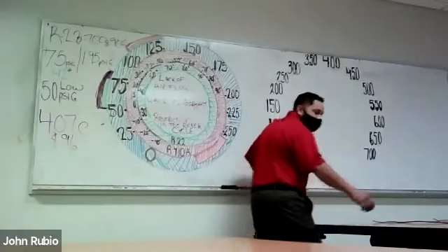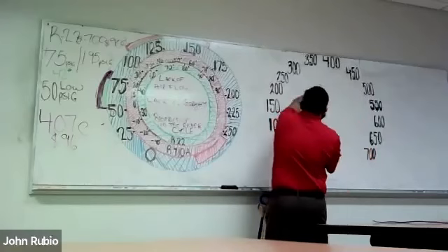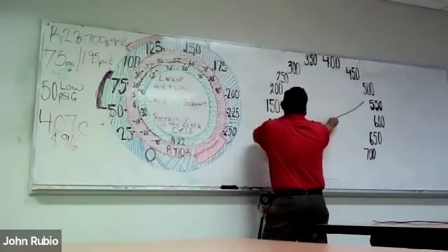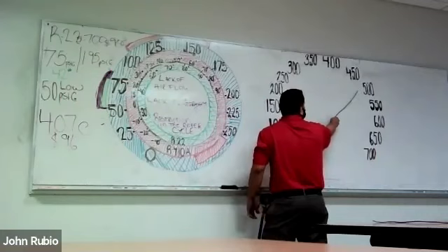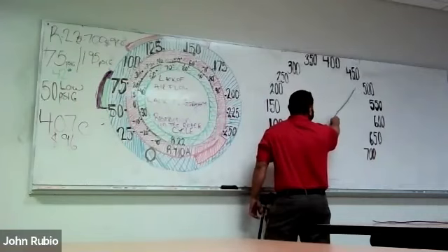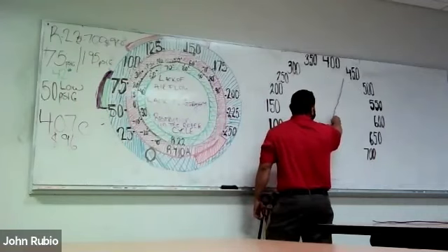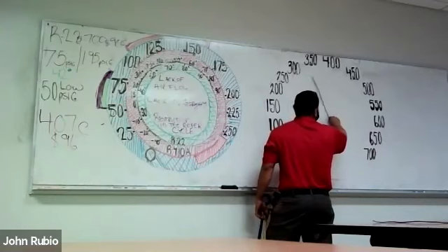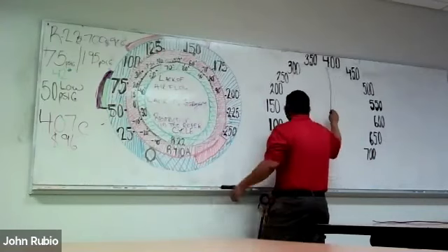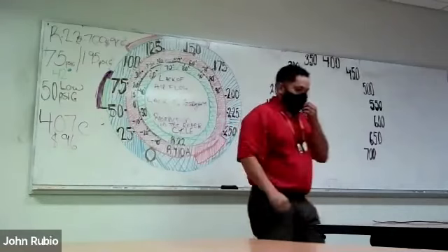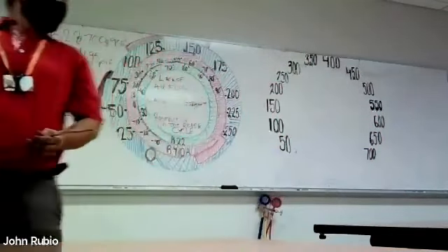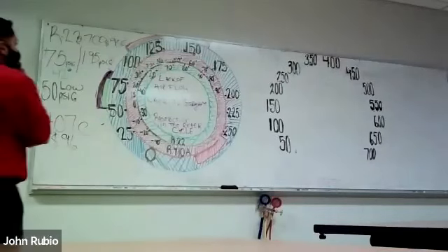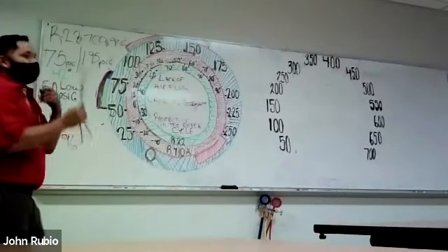And what'll happen is when you're in that case, when you're at 500, as you're releasing, the number will fall. As you're releasing, it will fall again. And once you finally clear it, it'll get to about 425, and then it'll slide back to its normal position. But because you didn't have this to tell you, you had no idea that you were frozen up or in a truly restricted position. Again, this is why the high side is important.